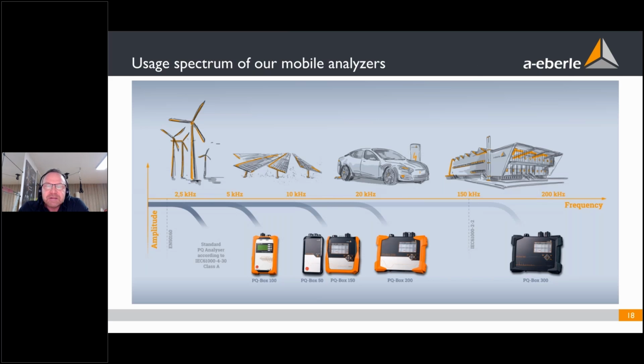For the use of our analyzers, or any other analyzer you are using, could be from Fluke, Janitza, anything, in power quality it's a must: the frequency you want to detect, you want to measure, the analyzer must sample at least twice the frequency of the signal you want to measure. So this is an old PQ-Box 100. We do not produce this box anymore, but many customers are working with the PQ-Box 100. This device has a sampling frequency of voltage and current of about 10 kilohertz. So the maximum limit is 5 kilohertz to detect disturbances.